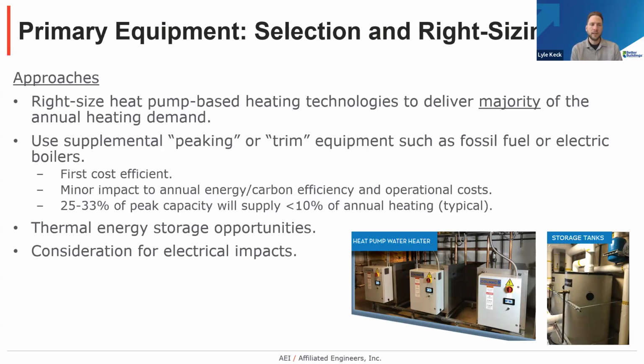And a rule of thumb that we use is that a quarter to a third of the peak heating capacity will generally supply less than 10% of the annual heat to your system. So again, finding that sweet spot, finding practical, first cost efficient solutions, and then having a minor overall annual energy penalty or operational cost penalty. Thermal energy storage is another key approach. For domestic heat pump water heating, best practice nowadays is to include some sort of storage, minimize the size of the heat pumps, and run those heat pumps more continuously. And thermal energy storage in general separates the demand side from the production side, which really opens up a lot of opportunities relative to peaking capacity and improving the reliability of operations.